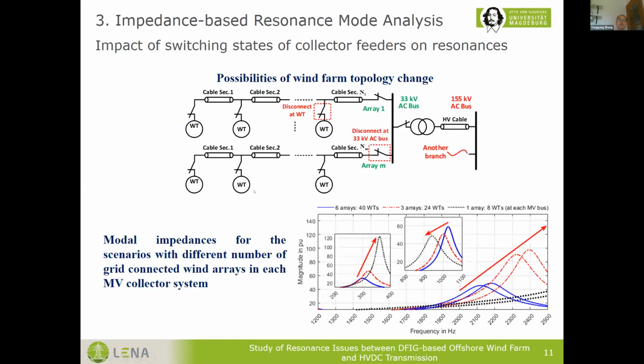This slide presents the impact of switching states of collector feeders on the risk of resonances. Practically, either individual wind turbines or the whole wind arrays can be disconnected from grid. For the case of disconnecting the collector feeder breakers, the modal impedances under different scenarios are shown here. As can be seen for the frequencies above 200 Hertz, the variation of the grid topology in the wind farm can lead to enormous variation of the resonance frequencies. And for the critical one array stay connected in grid scenario, larger resonance peak is observed at around 350 Hertz.